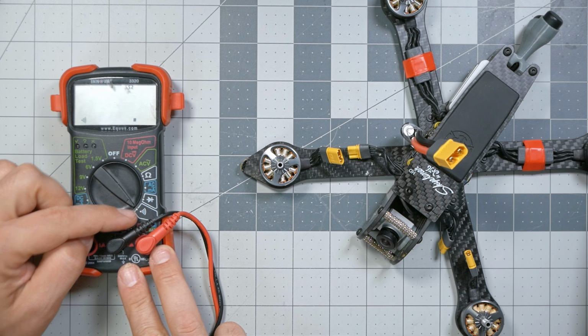Because we've identified that we don't have any obvious mechanical defect in the motor. We checked the motor to see if the shaft was bent or the bell was rubbing. The bearing felt okay. Everything seemed basically okay in that motor. But the electrical problems are much harder to figure out. So I'm going to put my multimeter into continuity check mode, and that's the mode where when there's electrical continuity between the probes, you get a beep. And normally that's how you chase down a short circuit. You test for continuity, and if there is continuity, then you have a short circuit, and that tells you where the short circuit is. But that doesn't work with brushless motors.